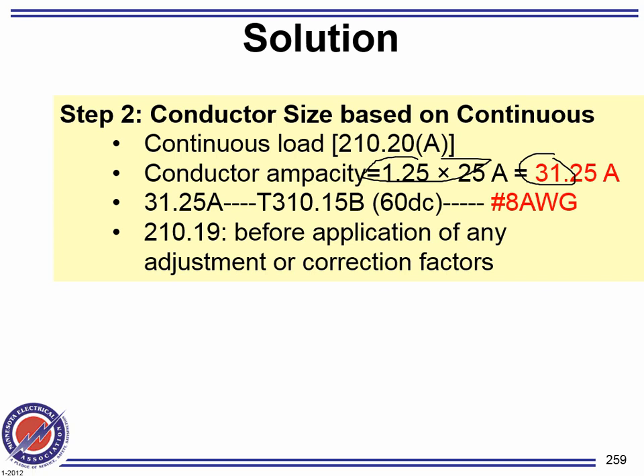Then you take this. Why did we go to the 60 degree column even though the installation is THHN? Anybody can tell me? Because the equipment is less than 100. It doesn't matter what the conductors are, normal operating. So that gives me number 8.